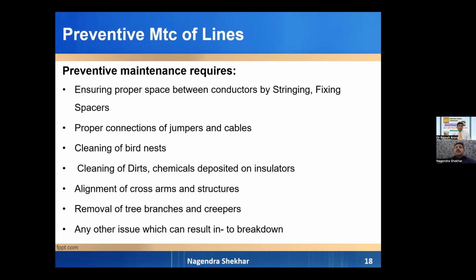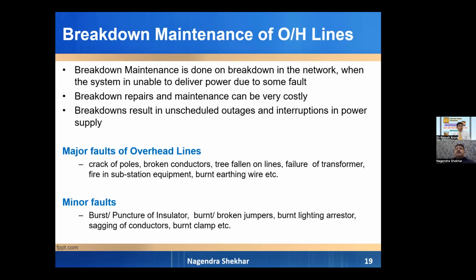Cleaning of bird nests, cleaning of dirt and chemical deposits on insulators, whether these are bushings or transformers or R-pin or other insulators. The alignment of cross arms and structures is disturbed because of storms and thunder during the rainy season, and that can be realigned. Removal of tree branches and creepers: tree pruning and removal of creepers is necessary. Any other issue, like thermoscanning and partial discharge, can result in a breakdown or a gap between vertical or horizontal spaces.